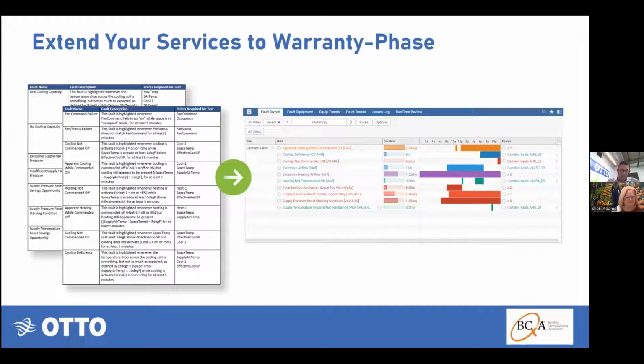Where we automated testing in the previous slides, that is what we call active analytics. We're actively creating various modes to create conditions and see if it works out the way it's supposed to. For automated fault detection, it's passive, so we're just sitting back watching the data. If certain things happen, we flag it as a fault. As opposed to alarms off a control system, these are multi-layered and have time elements to them. It can involve what's going on with the parent air handler, chill water loop conditions, hot water loop conditions. You can add all sorts of parameters in here to tell you when something is wrong. So that's wonderful about that.